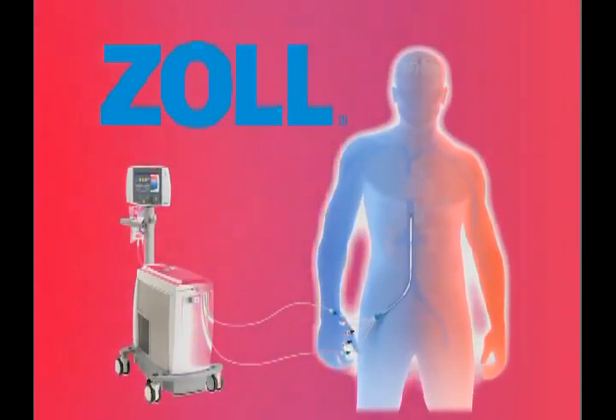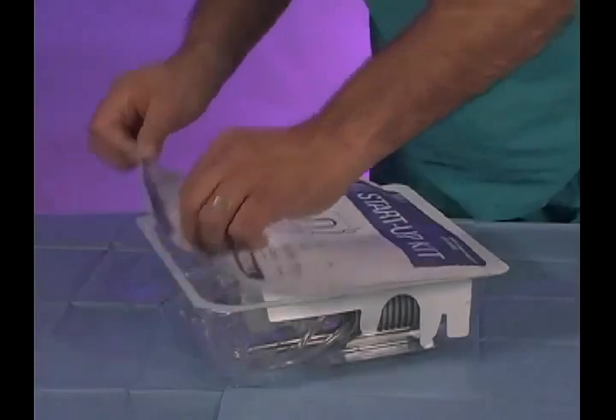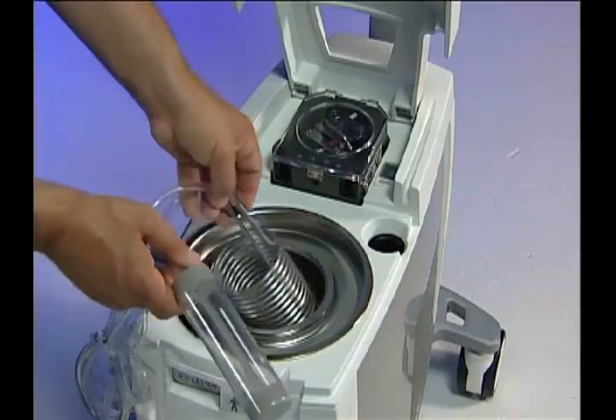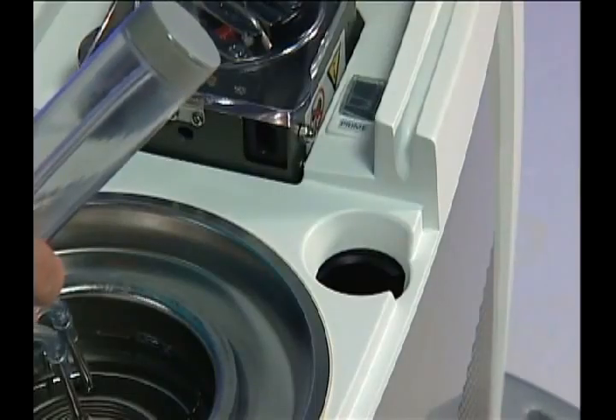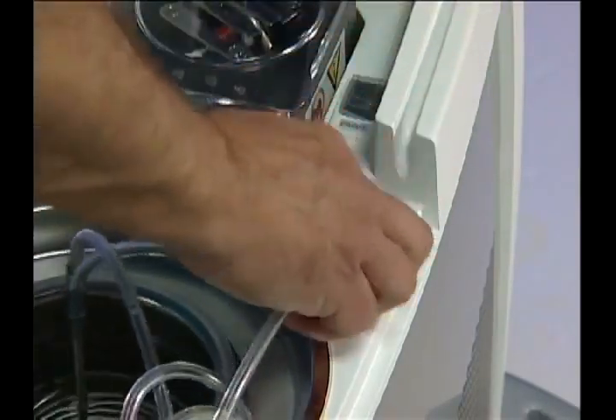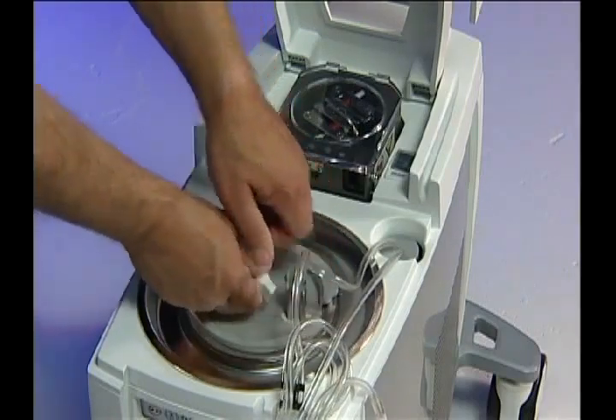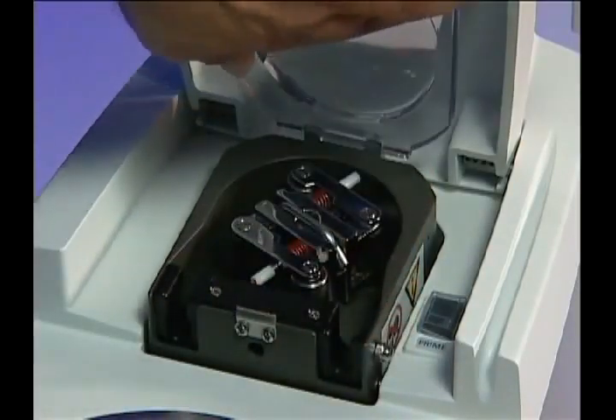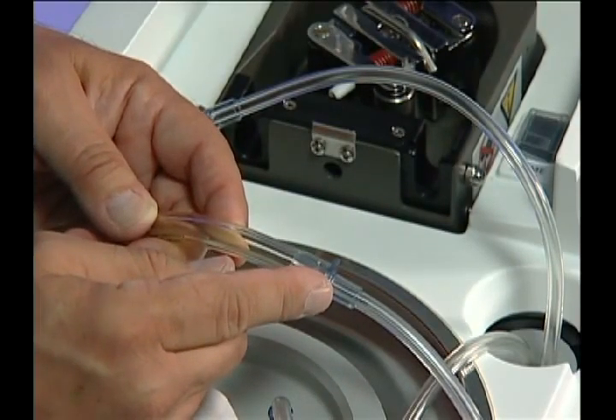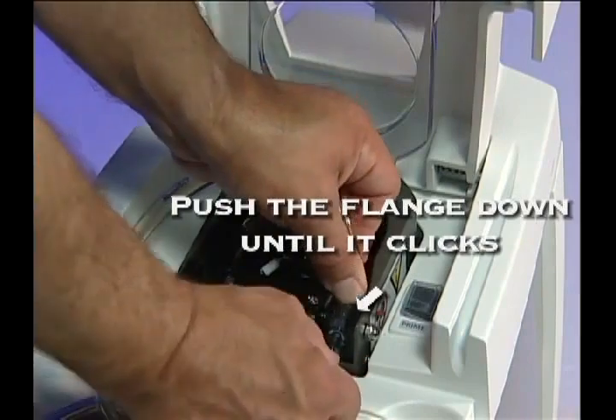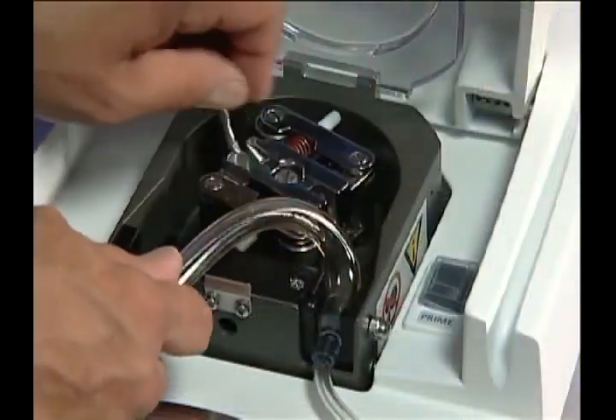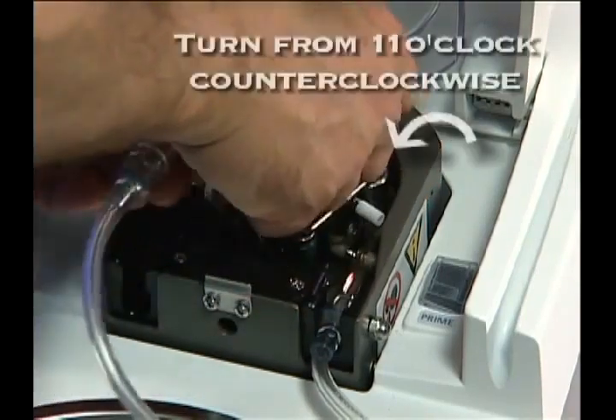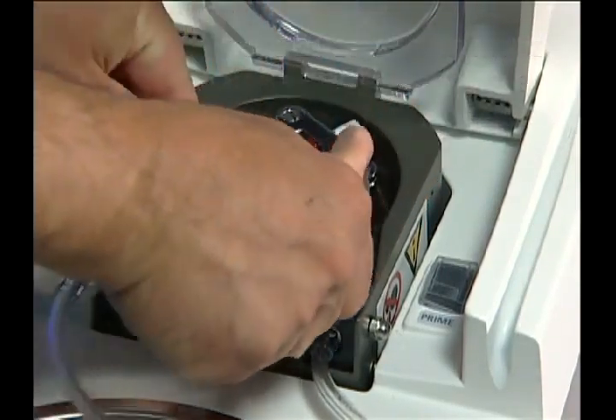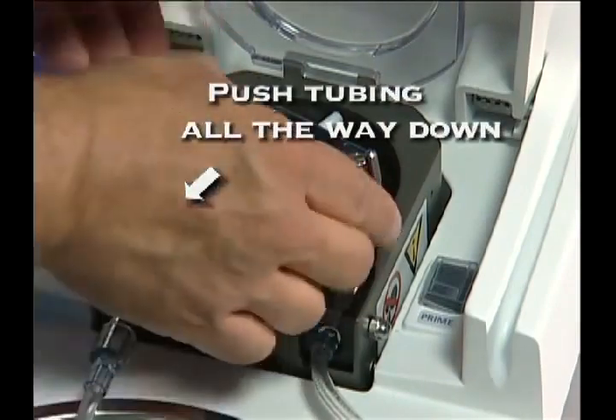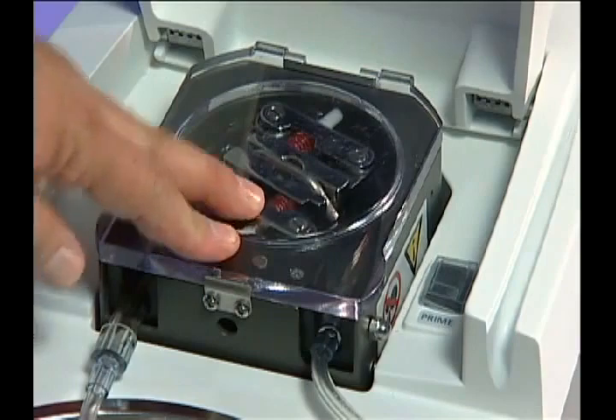This is a good time to install the tubing set. First, lift the top cover of the machine. Open the startup kit and insert the heat exchanger coil into the coolant well. Then place the air trap into the air trap holder. To load the tubing into the pump, locate the flange on the thick section of tubing. Place it into the slot on the right-hand side of the roller pump fixture. Slowly feed the tubing counterclockwise inside the raceway, approximately halfway down from the top, while simultaneously rotating the roller assembly. Then, firmly close the top cover of the pump.